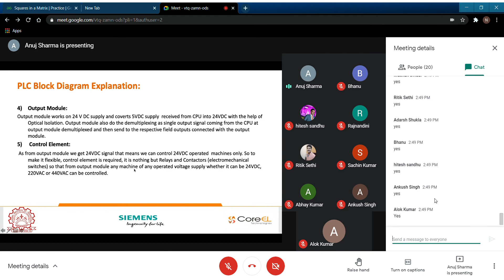And as from the output module we get a 24 volt DC signal, that means we can control only 24 volt DC operated machines. So to make it flexible, a control element is required, but with the combination of proper relays and contactors, we can convert this 24 volt into any kind of supply that we want, even 3-phase, 2-phase, any kind of supply, 220 volt or 440 volt, but through relays and contactors.